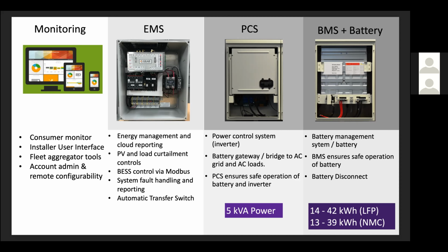There's BESS control via Modbus. So there's a serial Modbus connection from the EMS over to the battery to control battery charge discharge, as well as to poll for battery status information. There's system fault handling and reporting, as well as automatic transfer switch.